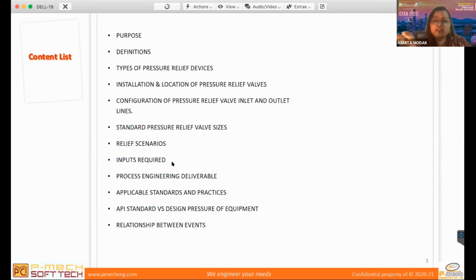But if you are working on a Shell-based project, Shell always emphasizes using their own standards. Shell has its own standards, so at that time the Shell standards have to be referred to. Then some ASMEs for non-API PSVs. You can refer to ASME, especially for boilers. Then API standard versus design pressure of equipment. We'll see here the different design pressures for different equipment, the criteria for selecting them, and the relation between the events.